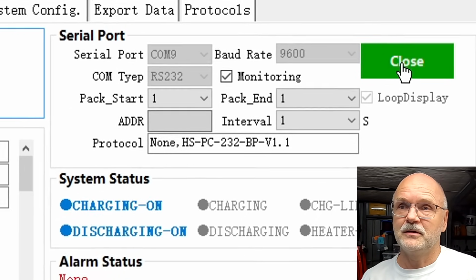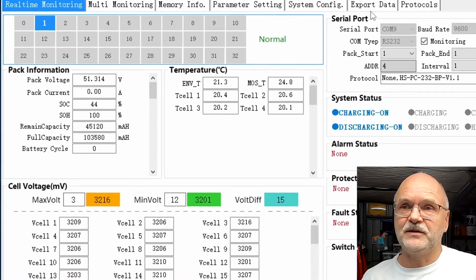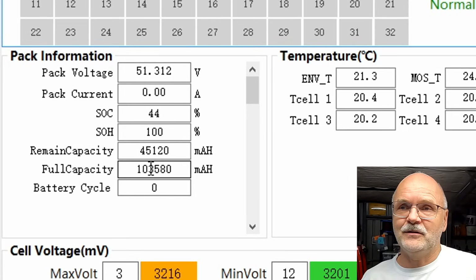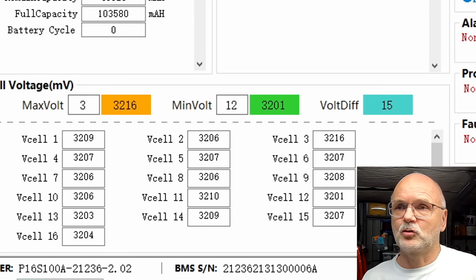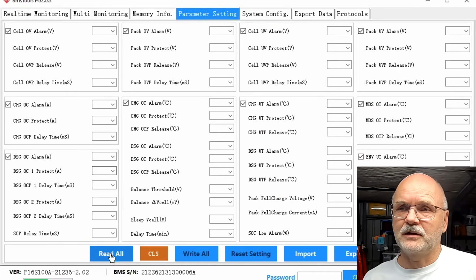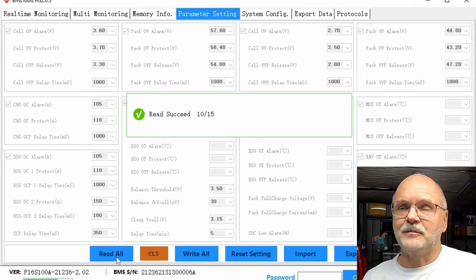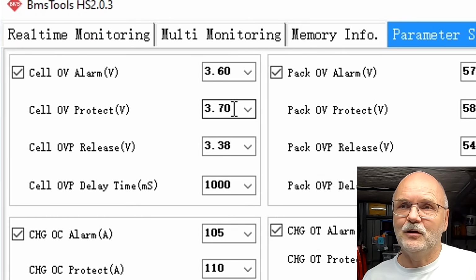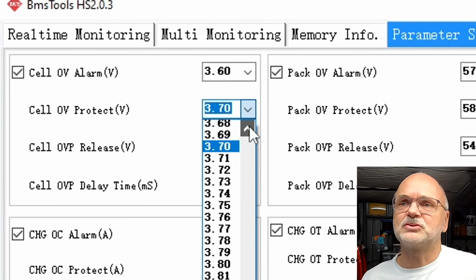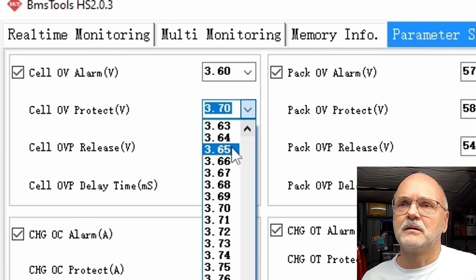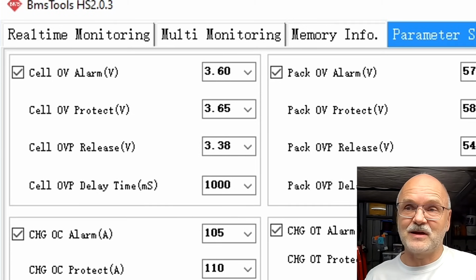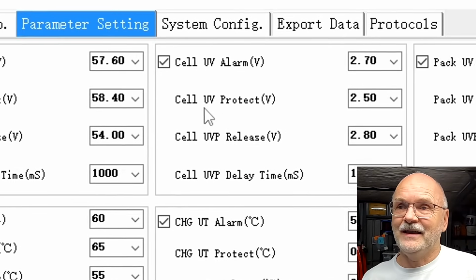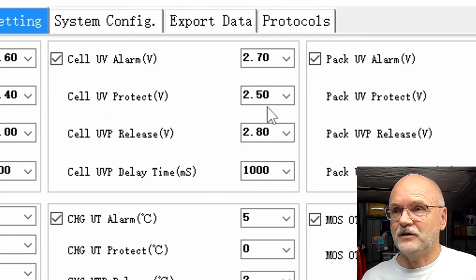So you click on open, starts the communication. We can see the voltage here, 44%, 103.5 is the full capacity. 15 millivolt deviation, that is all good. Okay, let's go into parameters here, click on read all, and immediately you can see the cell over voltage protection is a bit high, 3.7, it should be 3.65. So let's change this immediately. These are just the default settings the Pace BMS comes with, and you always need to check the cell over voltage protection as well as the cell under voltage protection, which is on 2.5 here, which is correct.